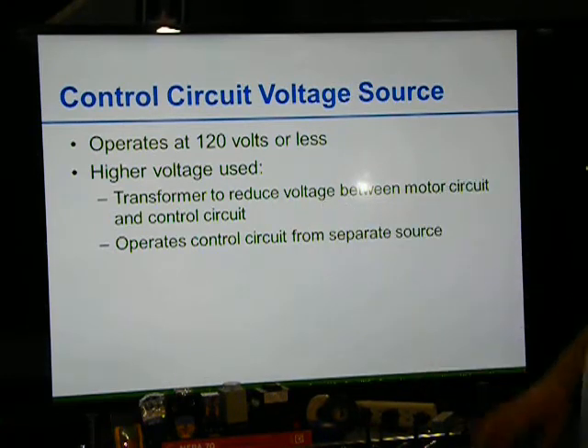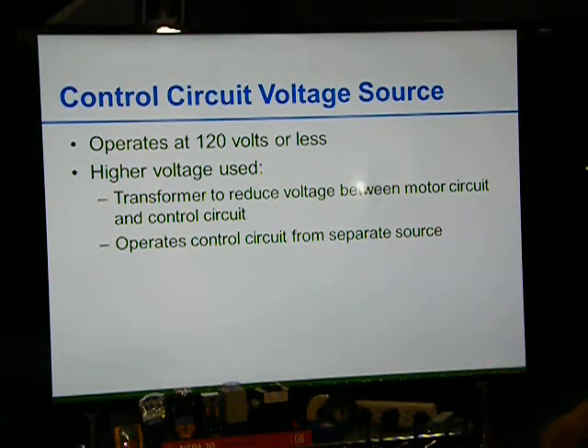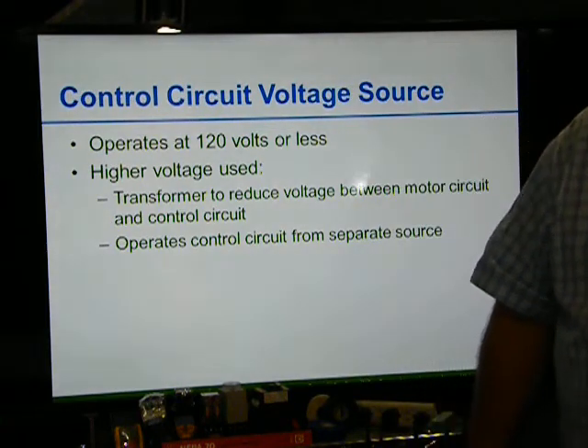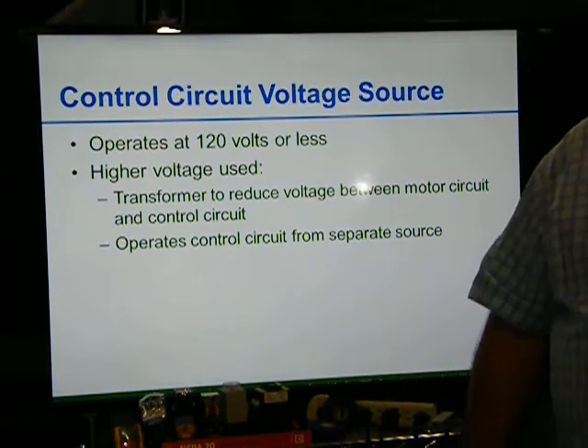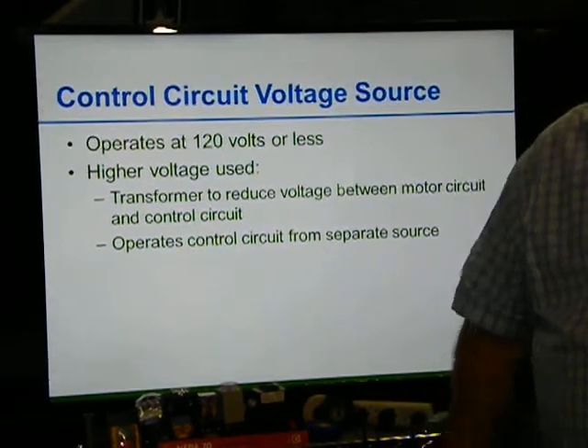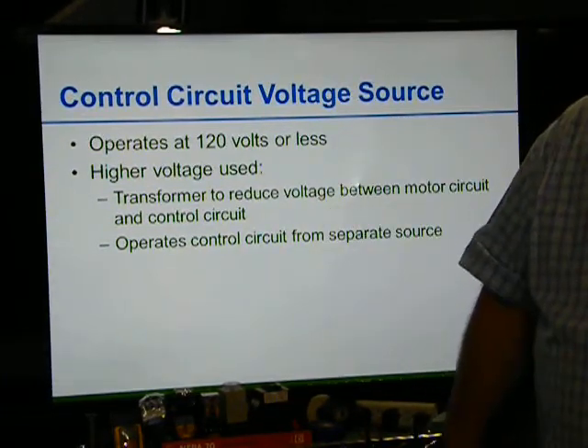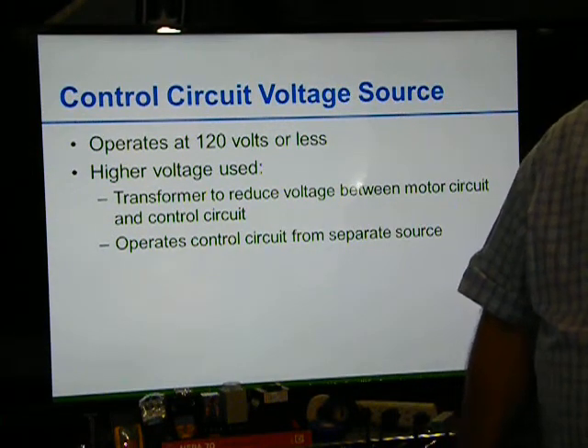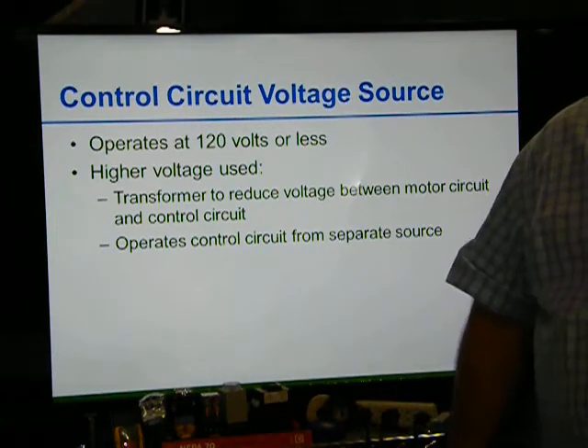Well, we can put in a transformer to reduce the voltage between the motor circuit and the control circuit, or operate a control circuit from a separate source. We talked about this last time, and there was a question that you had. So you can bring in a circuit from outside. You know you got lighting in a room, and your light is 120 volts. Well, you bring that 120 volts down and you control it.